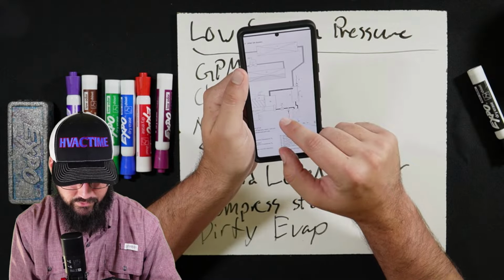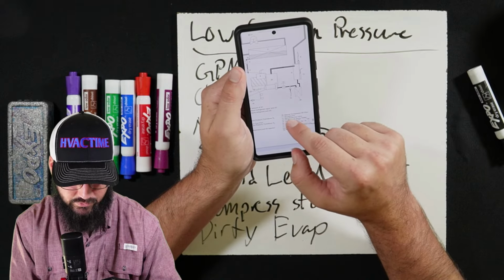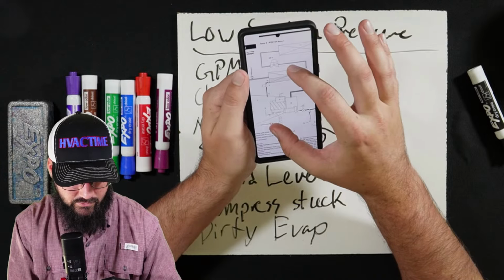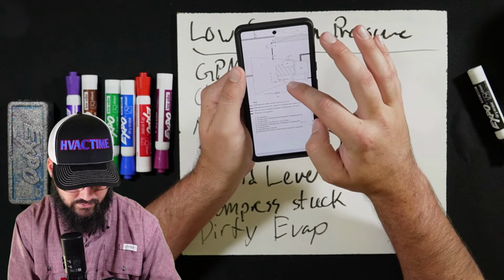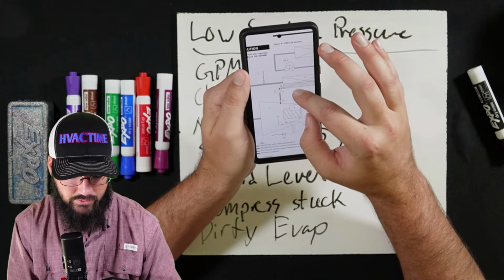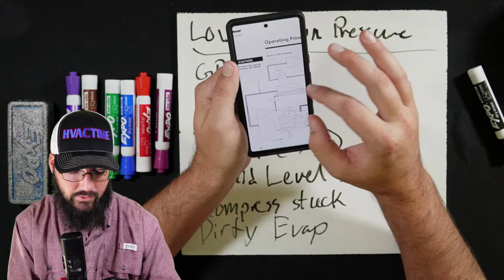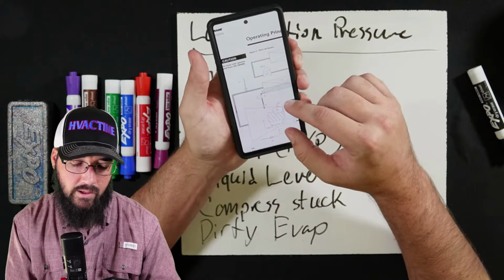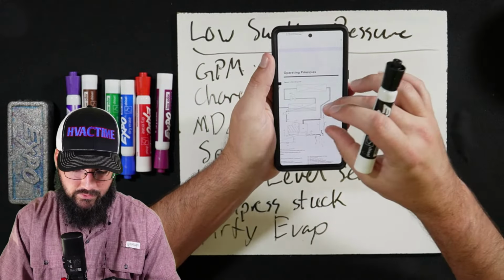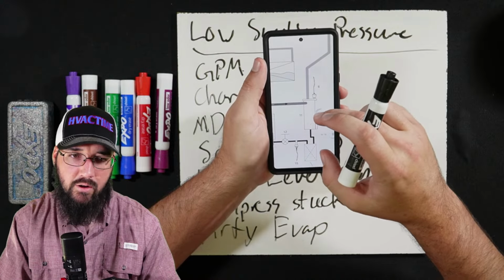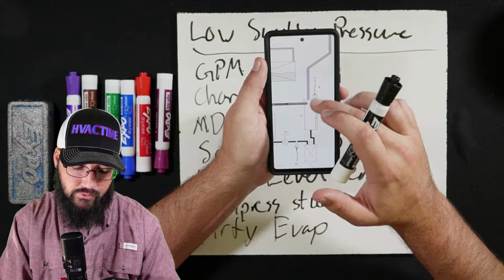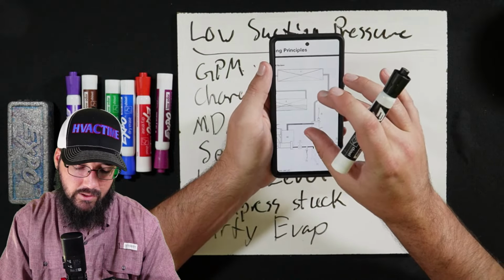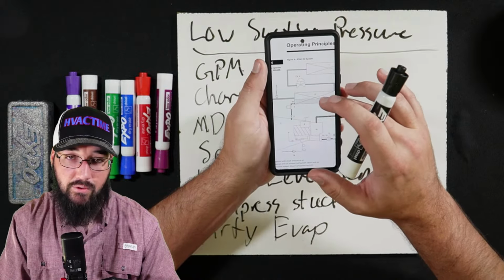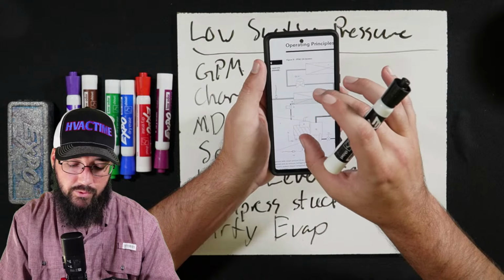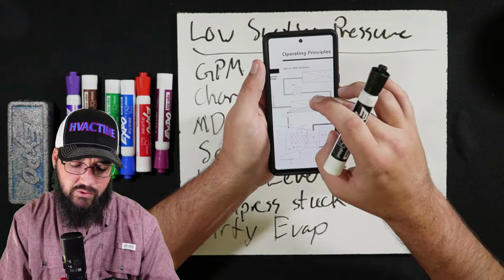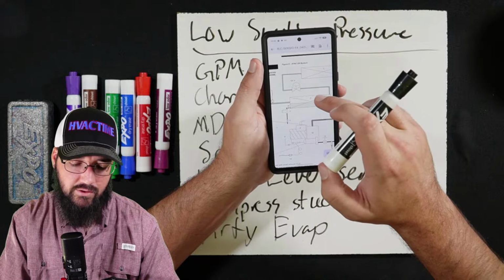Yes, okay. So number 11 here should be our oil separator. We can check that. Yeah, oil separator. But I think there's an eductor. Is that right? What is number 4? Evaporator oil return line. Yep, and filter. So there's a type of eductor system on this system. So that could be another potential problem. What could happen, just looking at this as our example, is some amount of oil does make it past the oil separator. So it's not 100% of the oil that gets captured. When that happens on this flooded style evaporator, the oil is going to collect in here. Actually, I say these are flooded. These are falling film because the EXVs on these feed into the top side of the evaporator.